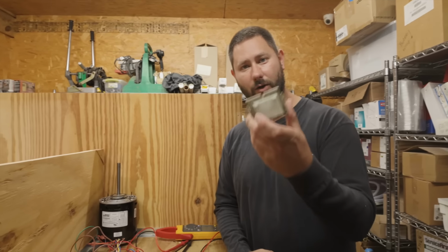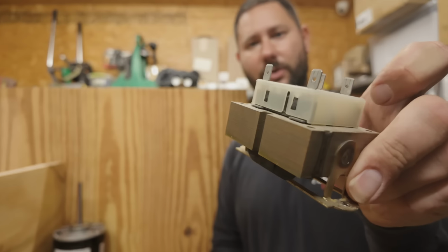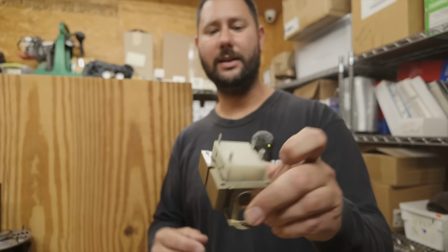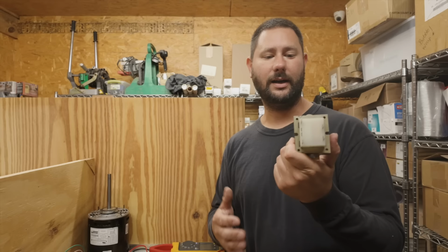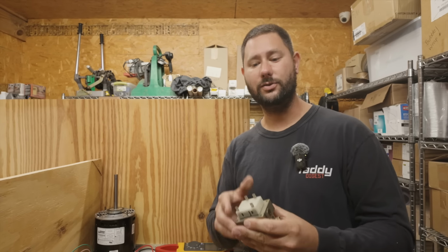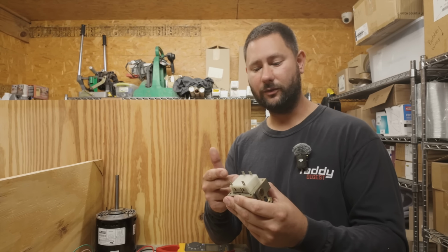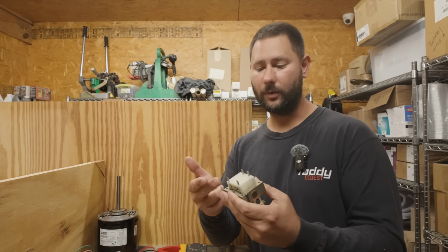Before we go over this little setup and use our meter, we're going to go over each component so you know what the component's called, what it looks like, and what it's used for. So first, this is a transformer. You have step-down transformers and step-up transformers. Typically, we use step-down transformers in the HVAC field, and usually it's 115 to 24 volt, or 240 volt to 24 volts.